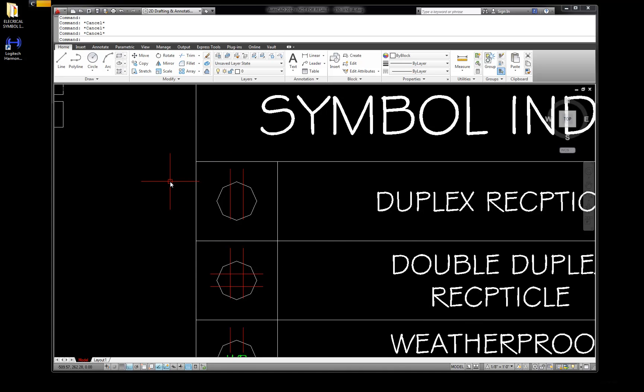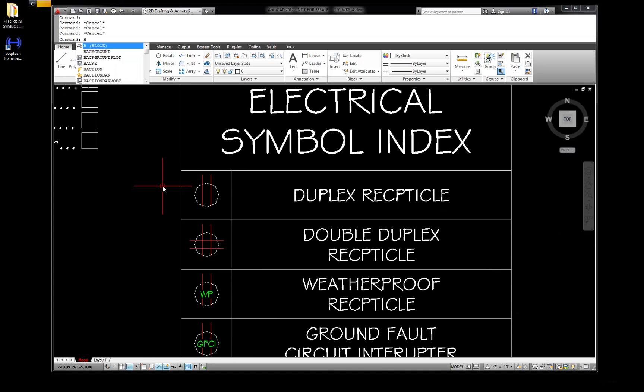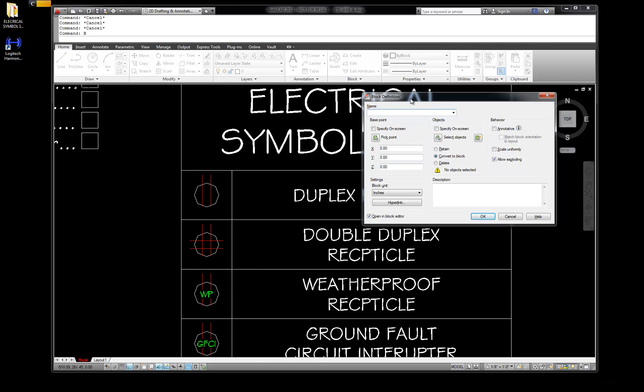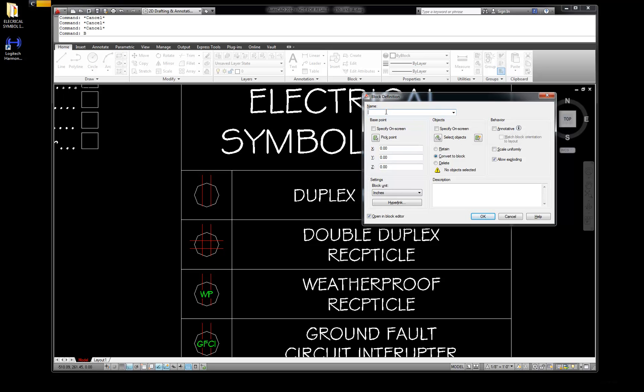Here's how we build a block - so easy. B for block. We get the block dialog box open. We're going to create a name for the block. We notice we have nothing in our block naming convention here, so I'm going to go to duplex. First of all, I know E because we're going to be making electrical symbols. If we were making plumbing symbols it would be P, landscape symbols would be L, architectural would be A, C would be civil. We're making electrical symbols so we're going to be on the E symbol.